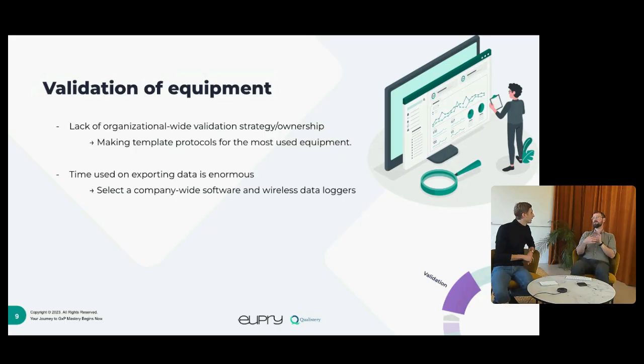Yeah, and I think also during validation of equipment, often the cost of introducing wired systems can outrun the benefits. Generally, a better terminology would be real-time data loggers. But in reality, wireless data loggers are so efficient, both in terms of cost, but also battery power and runtime. So today it doesn't really make sense to focus too much on wired data loggers. I think the time has, in my perspective, run away from wired systems, at least in some senses.